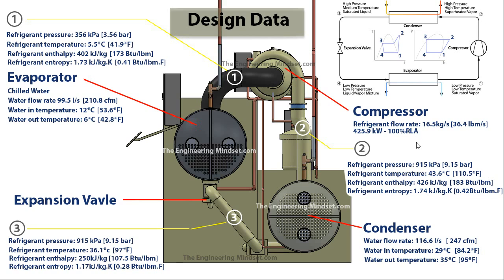At point three, located just after the condenser before the expansion valve, the pressure remains the same at 915 kilopascals. The temperature has reduced from 43.6°C down to 36.1°C, and there is a change in both enthalpy and entropy. At point three, the refrigerant temperature is 36.1°C (97°F), the refrigerant enthalpy is 250 kilojoules per kilogram (107.5 BTU per pound), and the entropy is 1.17 kilojoules per kilogram per kelvin (0.28 BTU per pound per °F).